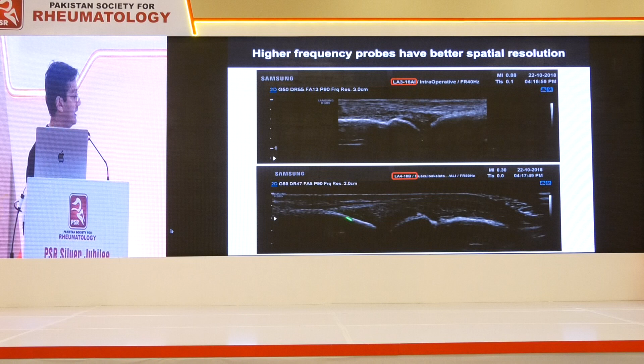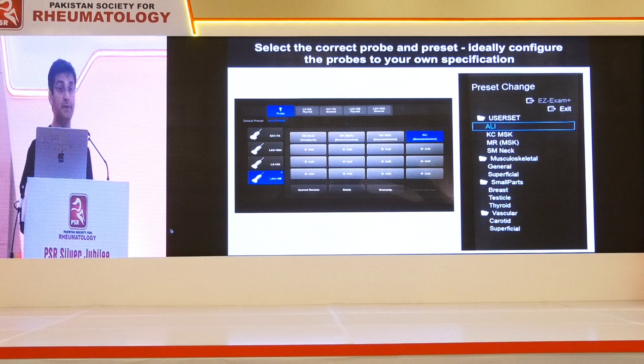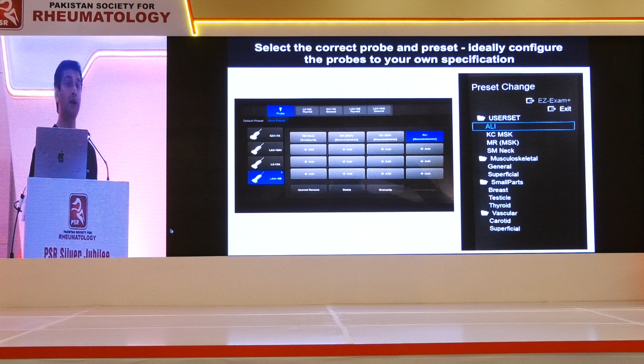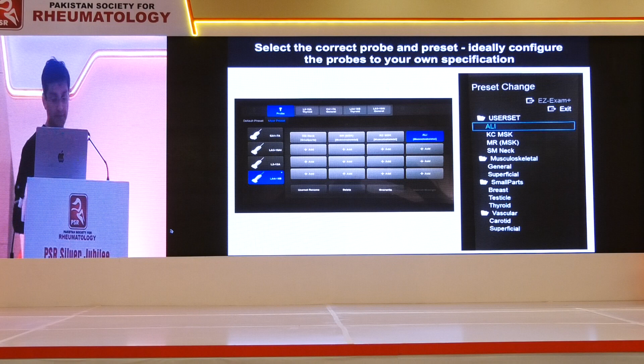The next thing is make sure you have the right preset. Now, most of the manufacturers will come with their own presets. They will have them predetermined. But I would urge you that when you get the new machine, if you are buying one, then bring your manufacturers back. Bring your application specialists in with you so that they can adjust the image, because every machine requires some calibration. It's often not plug-and-play. But you can adjust it. So I have my own presets here, and these are my other consultant colleagues. They all have their own presets of what they prefer.